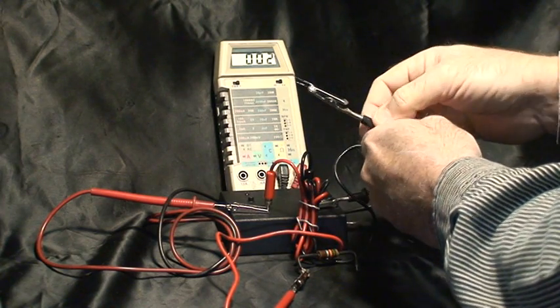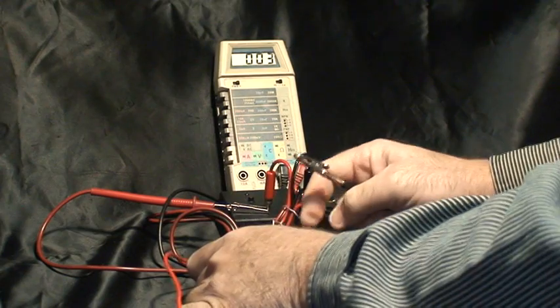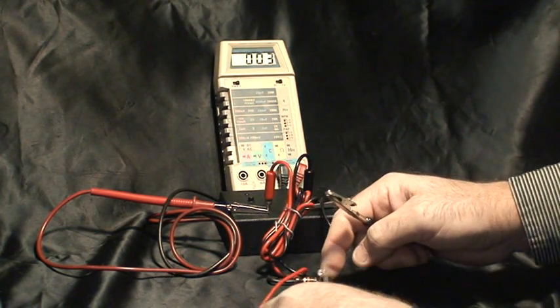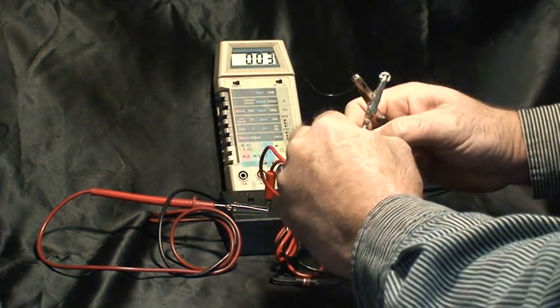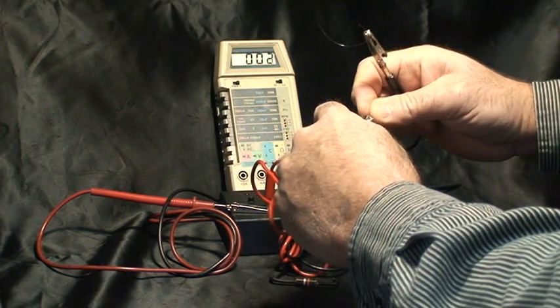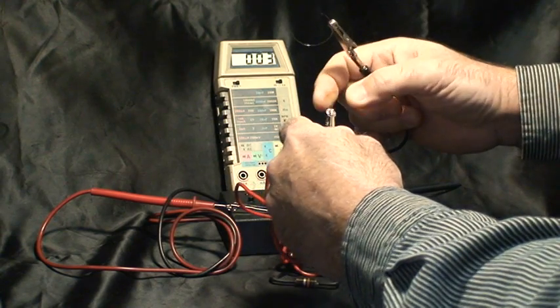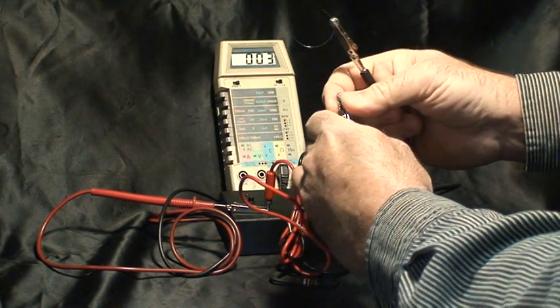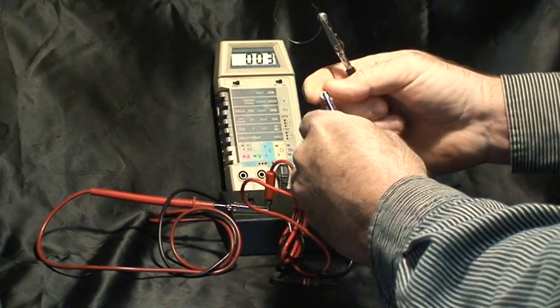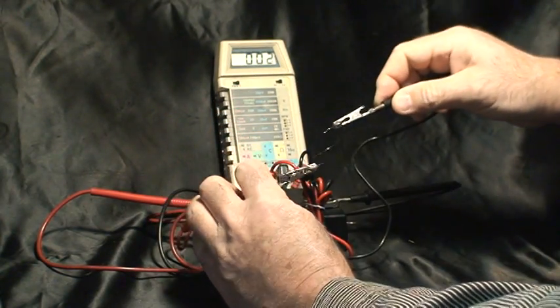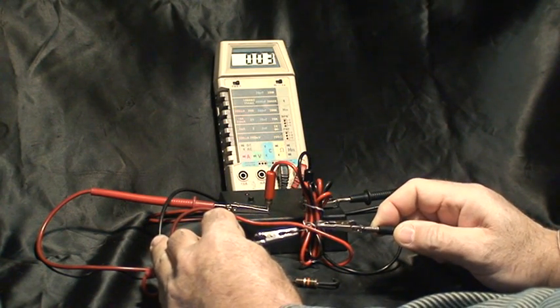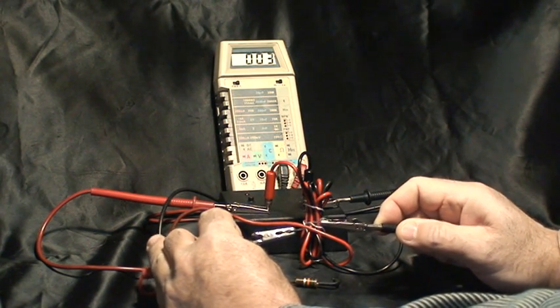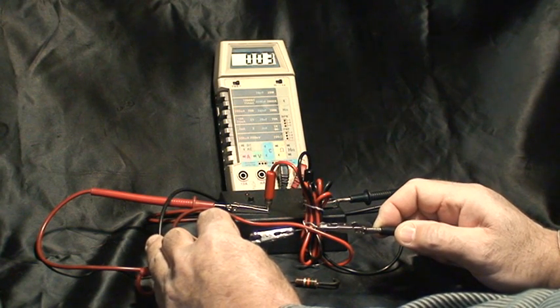When you weld with the other end, you want to get the wire to overlap. You don't want to tack the tips or the ends. Get it as short and tight as possible. You want to overlap it on top of each other. You don't want to tap the ends - you're not going to get a good weld. You want to place it side by side, adjacent.